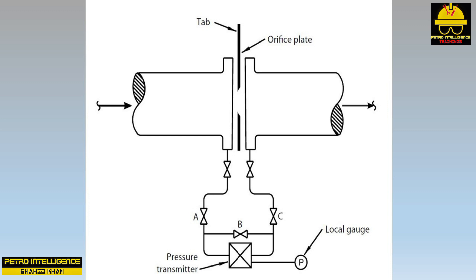Look at the tab sticking out of the orifice flanges. If the orifice plate is installed in the correct direction, there will be a number stamped onto the tab toward the flow — this is the orifice plate hole diameter. For example, if you see 0.374 stamped on the tab, the orifice hole diameter should be 0.374 inch.